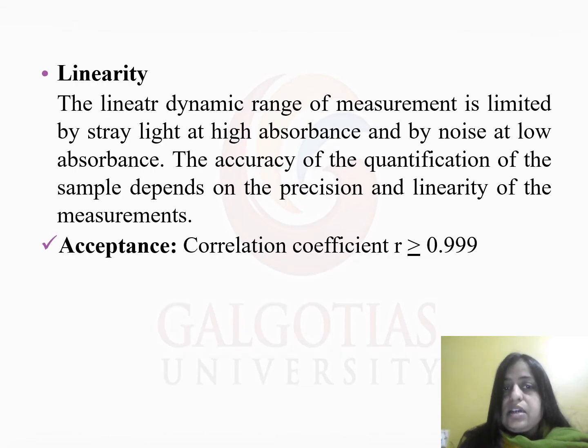Linearity: the linear dynamic range of measurement is limited by stray light at high absorbance and by noise at low absorbance. The accuracy of the quantification of the sample depends on the precision and linearity of the measurement. Acceptance: the correlation coefficient R must be greater than 0.999.